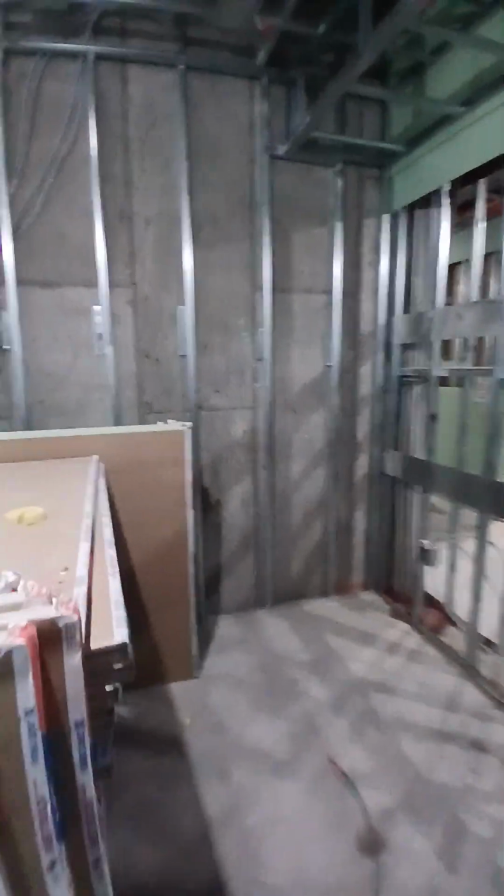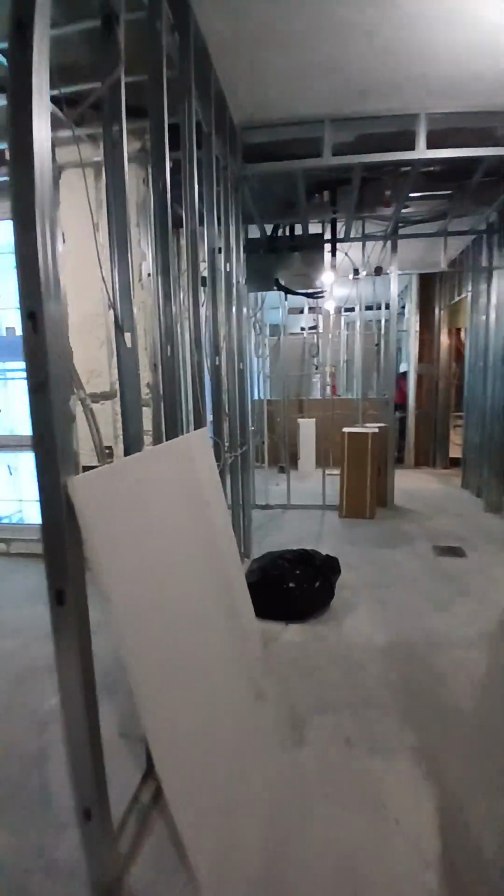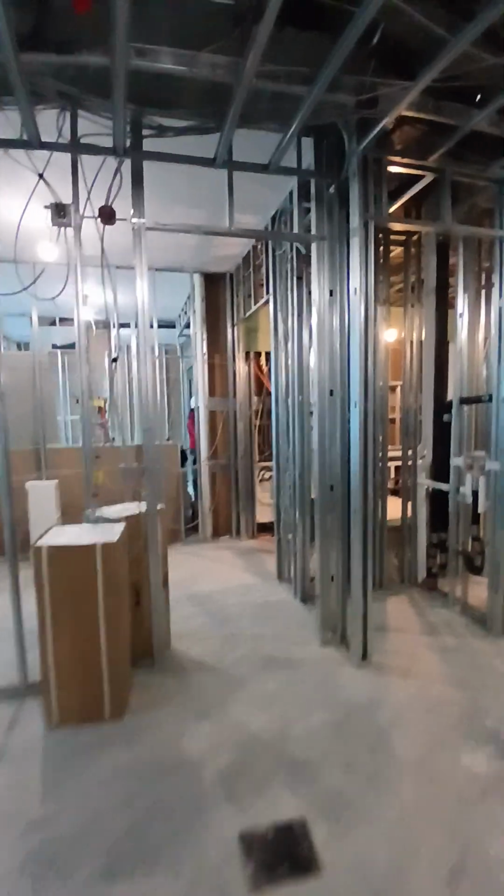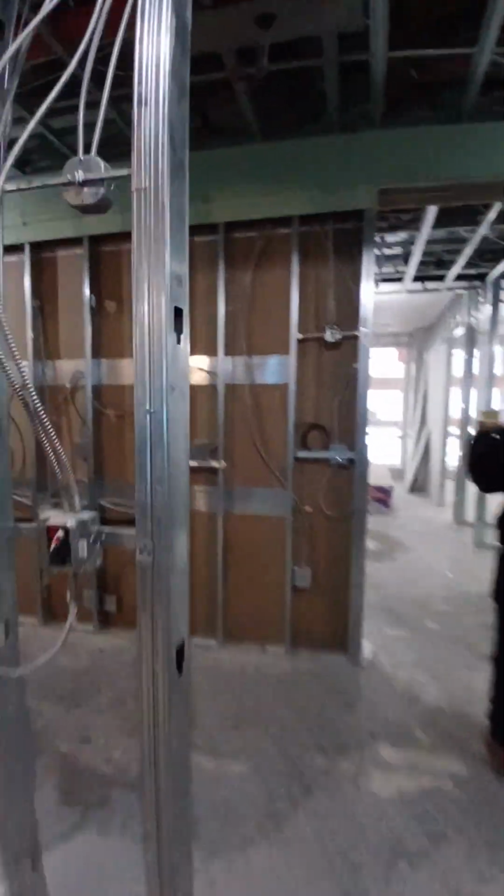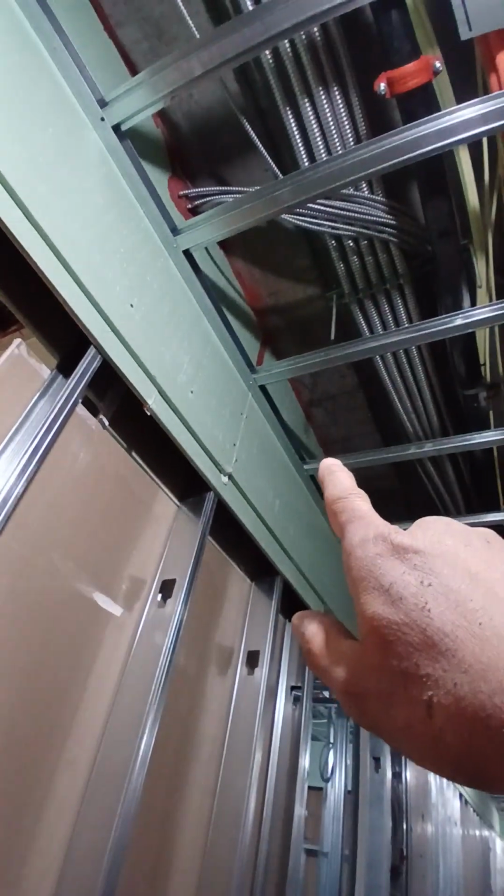The gap that is still there has to be sealed with fireproof material. That's what it's called, the fire stopping. Because we don't want smoke going from one floor to the next one, and we don't want smoke going from one area to the next one in the same floor, and that's why we have the fire stopping, fire blocking.